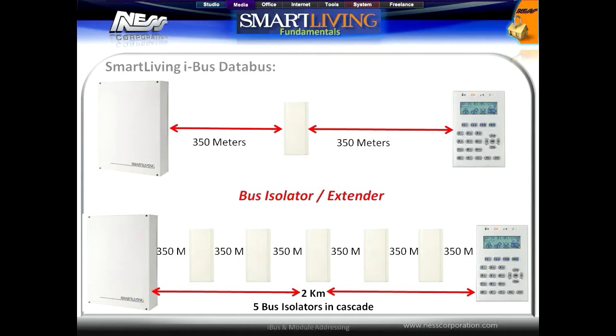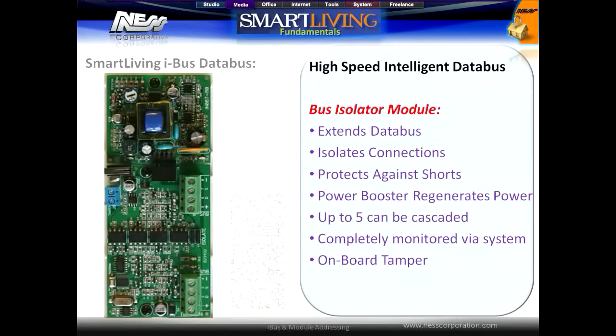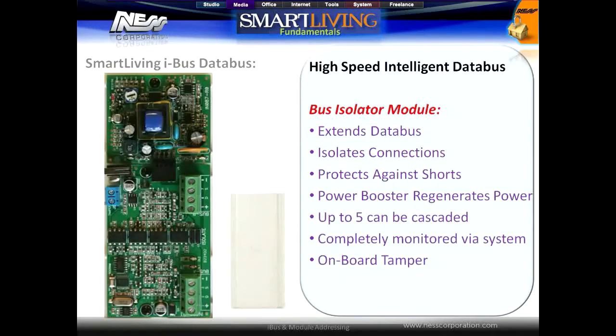It is possible to install up to five data bus isolators in cascade between any device and the main panel, and the panel will support a total of ten data bus isolators. The bus isolator modules both increase distance and isolate data bus branches, which is useful when running cables between buildings to protect against shorts bringing down the entire system. The onboard power booster regenerates power for long cable runs, and the module is also monitored by the system and can provide voltage feedback to the software.